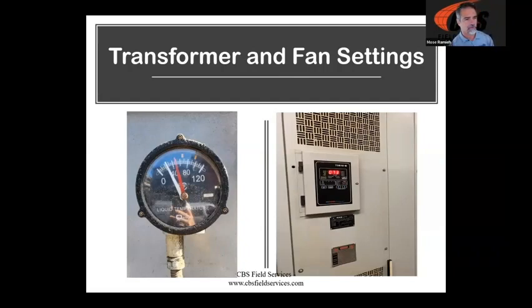Here's something that's really simple for me. I'm not sure exactly why this happens, but when we walk around or start up a new substation, are we looking at our temperature gauges? Are we making sure our fans are working? I'll cover why fans are important on our transformers in just a second. But I just want to point out whether you've got a gauge type or an electronic type of fan package. This is a gauge coming out of a substation outdoor transformer. For any of my friends online that have an indoor transformer, you're probably familiar with one or both of these types of temperature gauges.